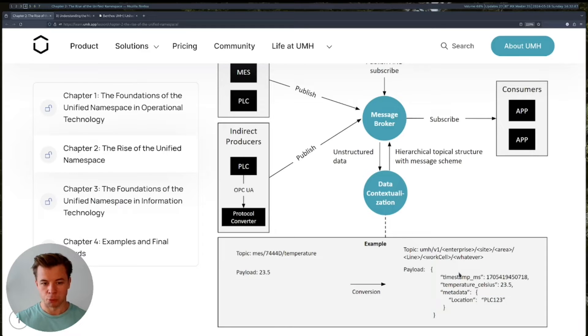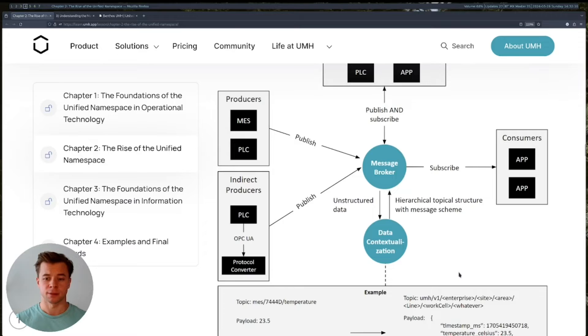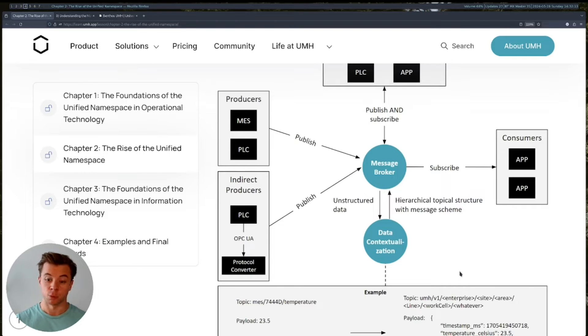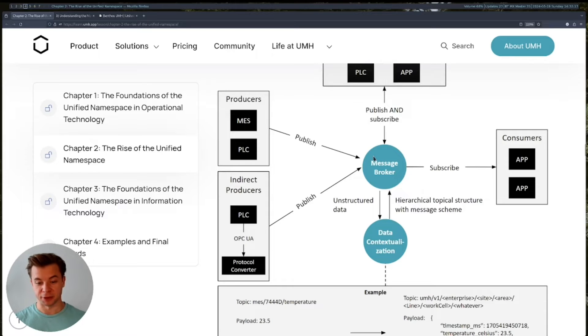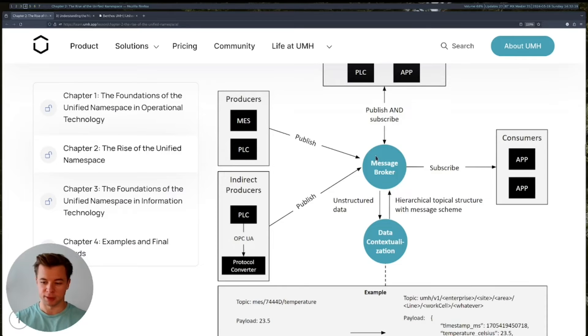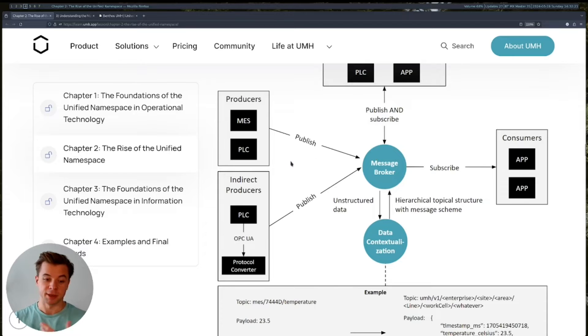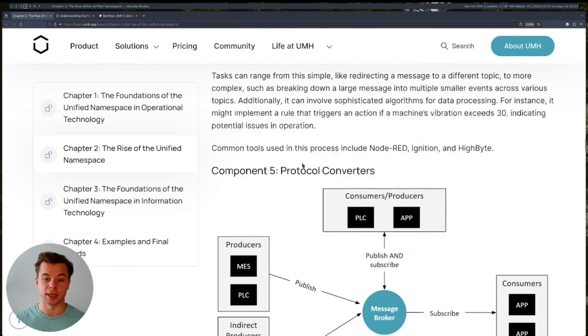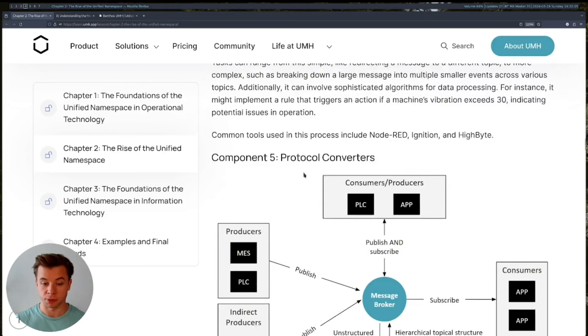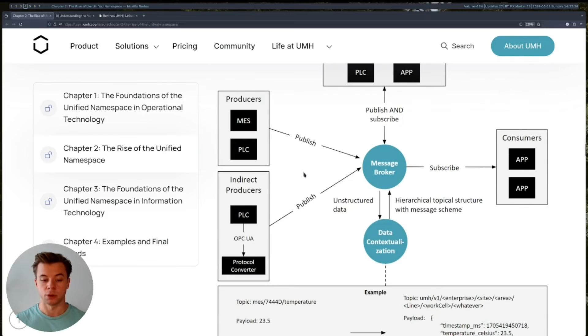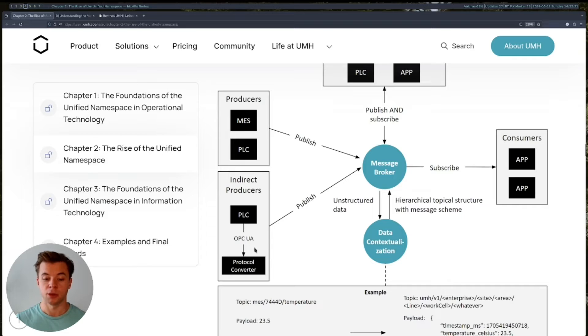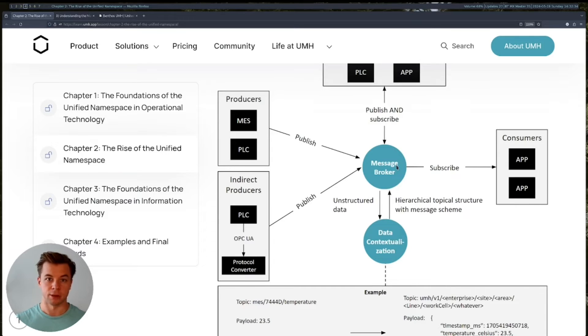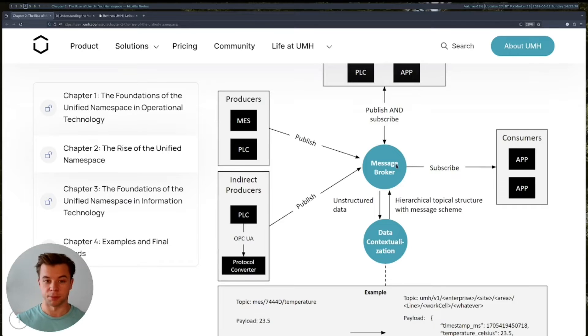But what if our data is not initially published as MQTT? We are using an MQTT broker, so the protocol that communicates the data should be MQTT. Well, if it's not in the beginning, then we will have to use a so-called protocol converter that will convert the initial protocol of the data, for instance OPC UA, into MQTT, so that it can be understood and written by the broker.